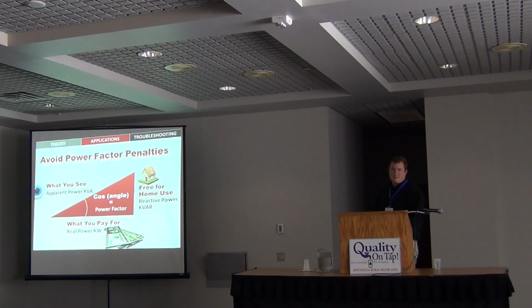Reactive power, that's the imaginary power part. That's what the utility companies don't like you to have very much of, because they need to supply that. They need to supply kVA. That's basically the combined vector sum of these two. They need to supply kVA to you, and so a lot of times you'll see utilities have a power factor penalty if your power factor is below 0.9.